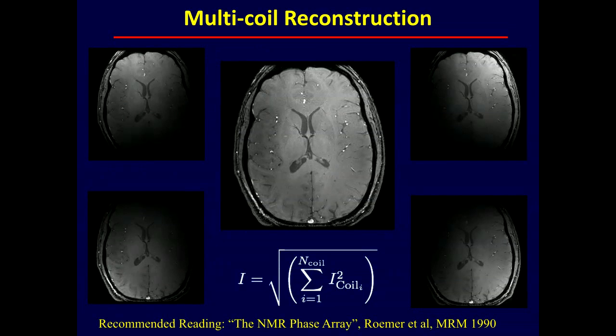So far there's no parallel imaging involved, but by doing that we can improve the SNR, because these coils are not sensitive to the entire region. For example, this coil is not sensitive to here, and it's not sensitive to the noise here as well. So if there's noise here, it's not going to be picked up by that particular coil element. That's why these surface arrays or more specialized multi-coil arrays improve your SNR compared to your body coil. Just keep that in mind. That's one benefit without parallel imaging.